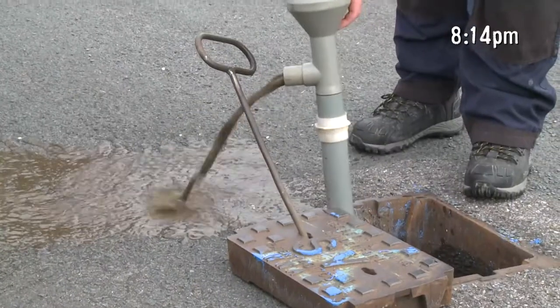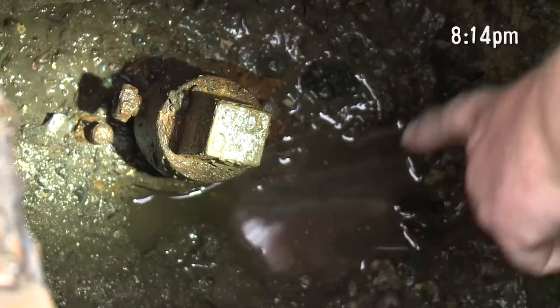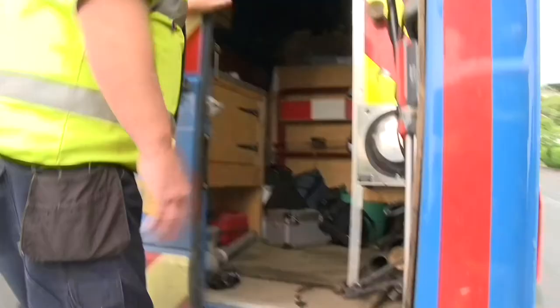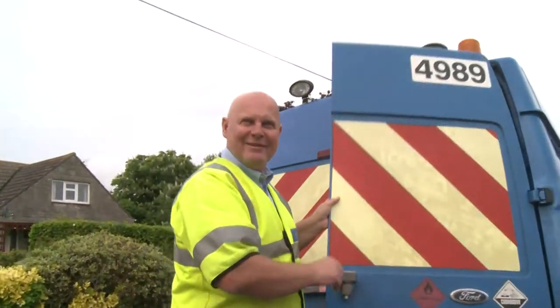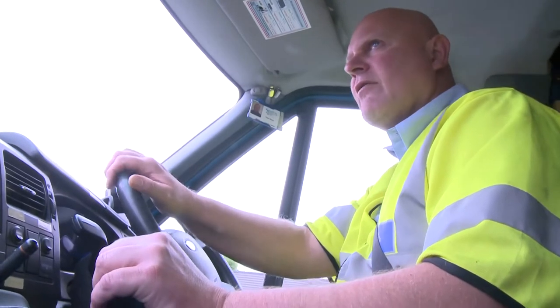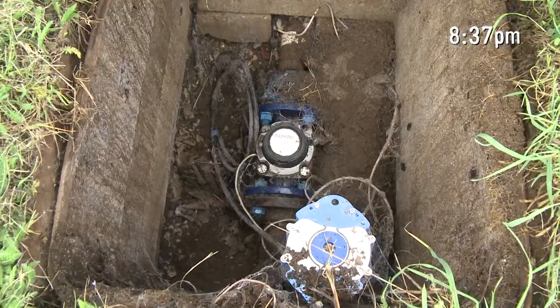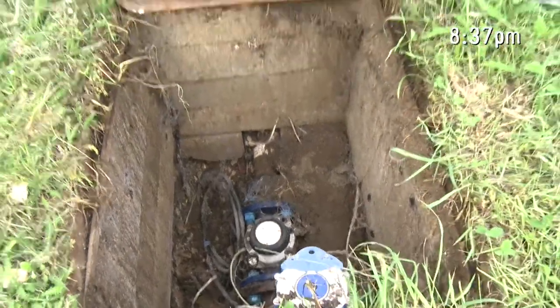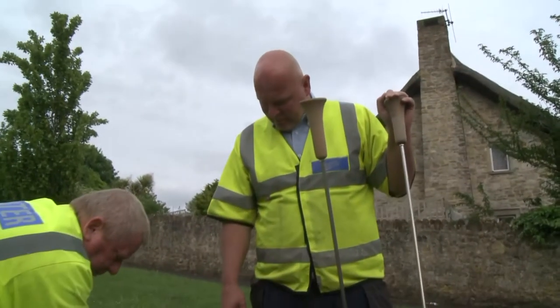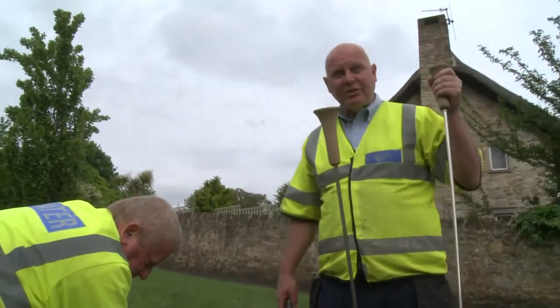So I'm just looking to see where the water is coming from, where the leak is coming from and the noise. And as we can see, the water is leaking from the top of the valve. That's another leak found, and on to the next job. We're going to have a look for a leak on a four-inch main. This could be the noise that we're looking for, but as it's a holiday park, it's probably still being in use. So we'll have to come back and check this at night when there's less usage about.